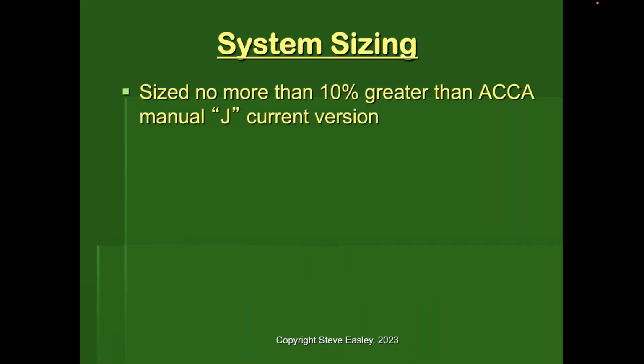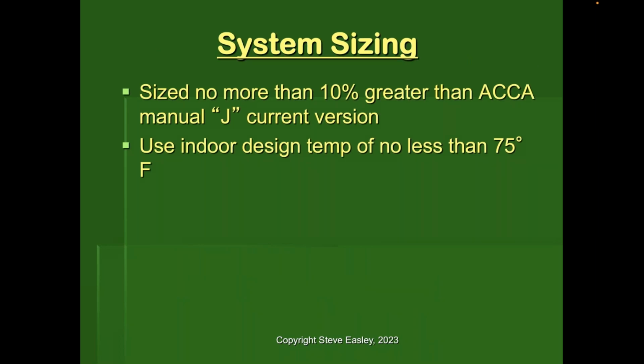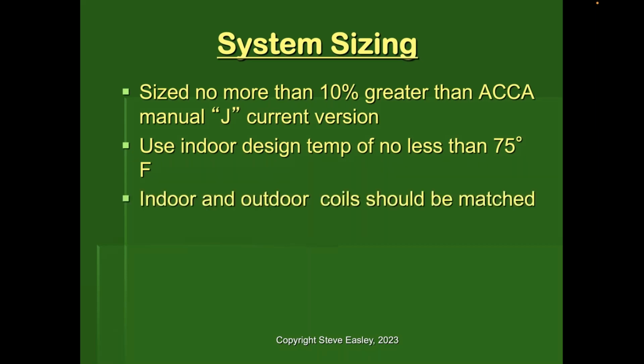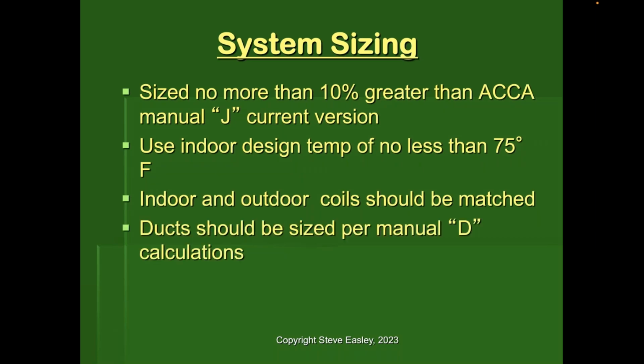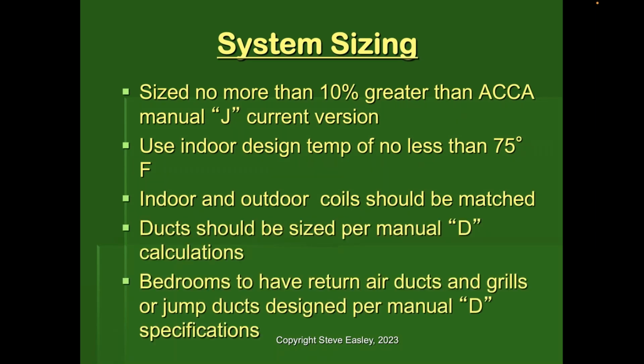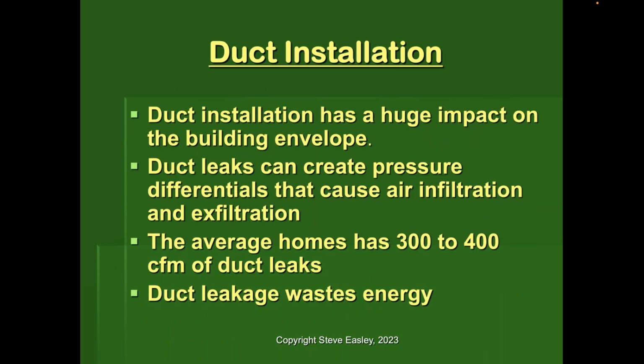So the bottom line is no more than 10% greater than the Manual J calculation. We want to use indoor design temperatures that are realistic for the area you live in. All an HVAC contractor has to do to oversize your system is give you a lower design temperature for the summer sizing. Then, indoor and outdoor coils need to be matched. Size ducts according to Manual D, and of course make sure that return air and supply air ducts are designed according to Manual D specifications.